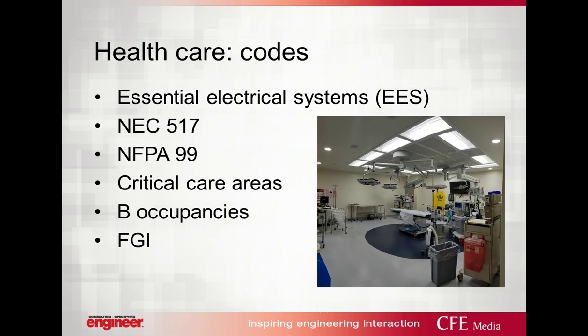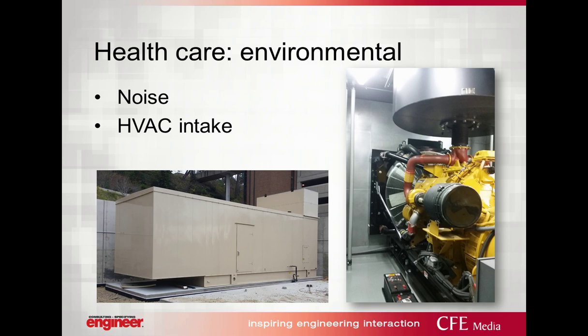NEC 517 also defines categories of the patient care space as 1, 2, 3, or 4. A simple way to think about it is like this. If people could die if the system fails, it's category 1. If they could be severely injured, then it's category 2. If they're made uncomfortable, it's 3, and if it's just an inconvenience, then it's category 4. So regardless of what your occupancy type is, if you have a category 1 or 2 space in your building, as defined by 517 for patient care, it'll have to have emergency standby power. You'll see B occupancy surgery centers that you'll assume it's a B occupancy, but because it contains category 1 and 2 spaces, it has the requirement for emergency power.